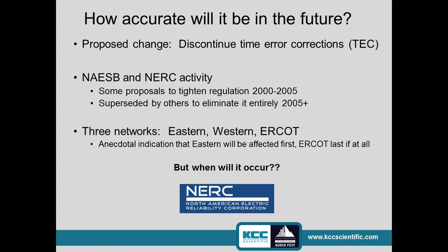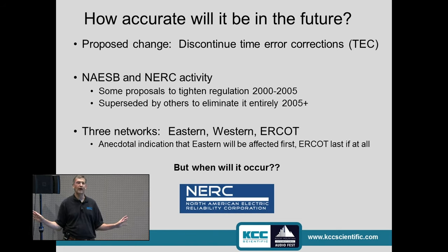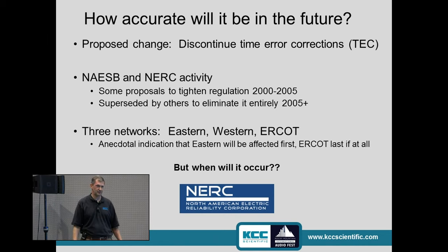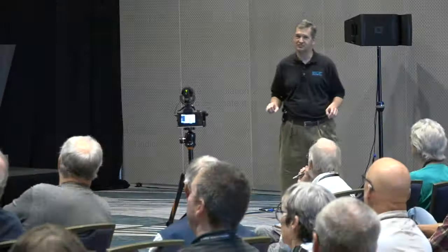How good will it be in the future? There's this thing called TEC — Time Error Correction. That was one of the primary purposes of controlling the line frequency: so that electric clocks could proliferate as basic time sources. Does it mean that the line frequency is exact at any given point in time? It means that over about a 24-hour period it'll be right. But in between, no way — it can vary by tenths of percent over that time.